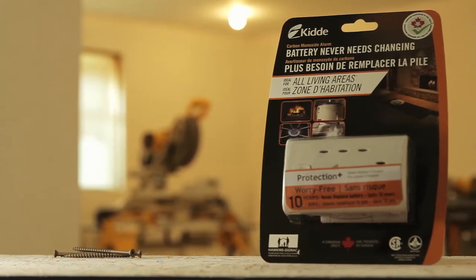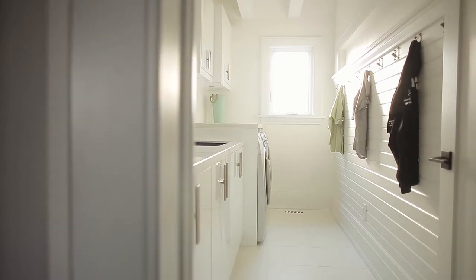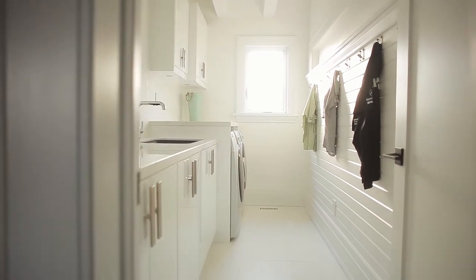You can't park these sensors right next to appliances or fixtures, because you'll get a lot of false readings. On the bedroom floor we do have a laundry room and a dryer, but it's not gas. If it were gas, I would still park the sensor in the hallway.